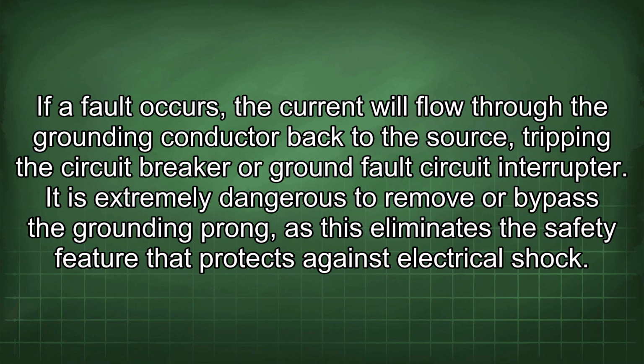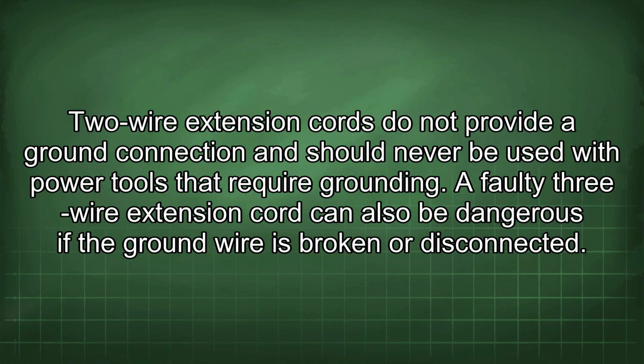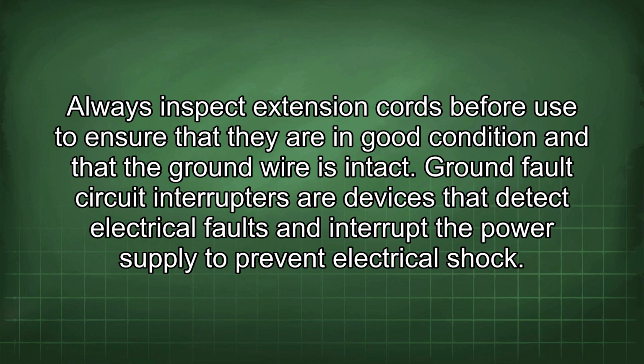It is extremely dangerous to remove or bypass the grounding prong, as this eliminates the safety feature that protects against electrical shock. 2-wire extension cords do not provide a ground connection and should never be used with power tools that require grounding. A faulty 3-wire extension cord can also be dangerous if the ground wire is broken or disconnected. Always inspect extension cords before use to ensure that they are in good condition and that the ground wire is intact.